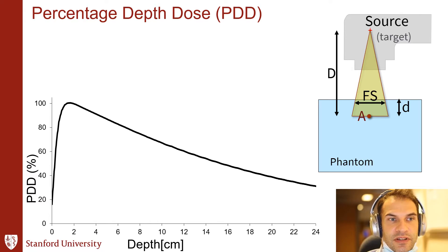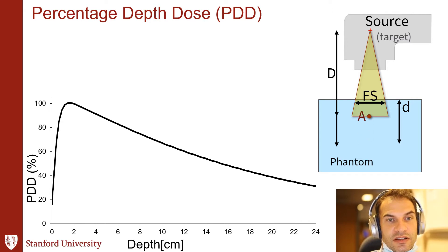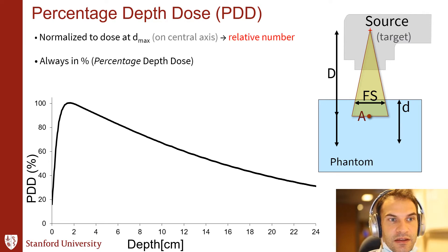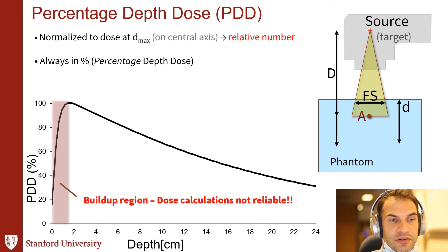The percent depth dose describes how the radiation behaves as a function of depth — when you have a detector in a water tank underneath a megavoltage radiation beam. We increase the depth of that detector by keeping a constant SSD, increasing both the depth and the distance from the source to our point of interest, by keeping the surface of the water tank at the same distance from the radiation source. These curves typically normalize to D-max. D-max is the depth of maximum dose and it's 100% on the PDD curve, always expressed in percent.